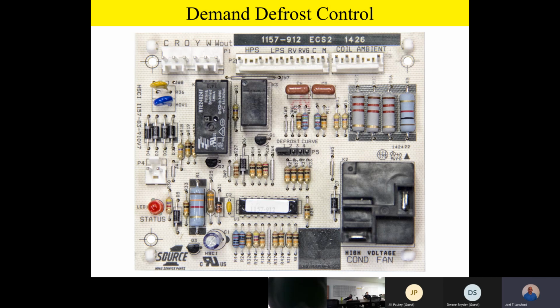Once the coil temperature reaches about 30 degrees, that switch is going to close on a drop of temperature, and then it's going to start timing the amount of run time after that switch closes. So here you've got this heat pump outside. It's in the heating mode of operation. The outdoor coil's cold. It's starting to build up some ice. Once that outdoor coil reaches about 30 degrees temperature, that little switch closes on a drop of temperature. Once that switch closes, it's a physical switch, it's 24 volts, click.